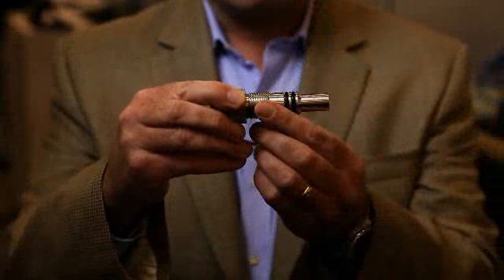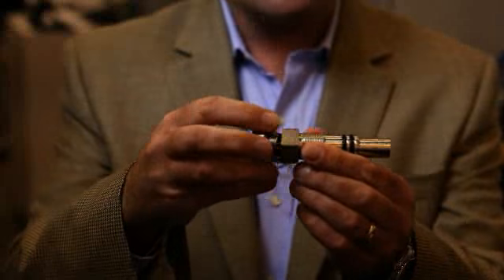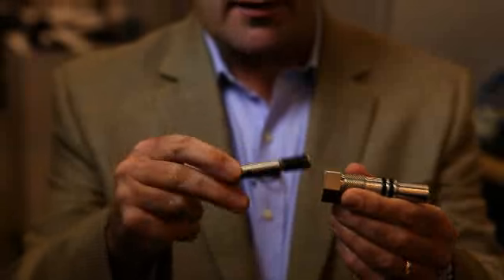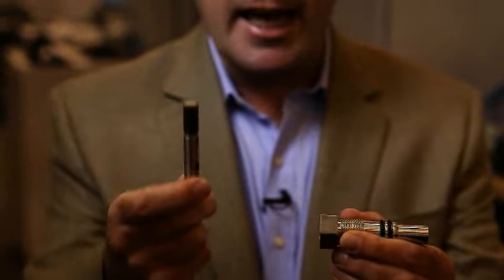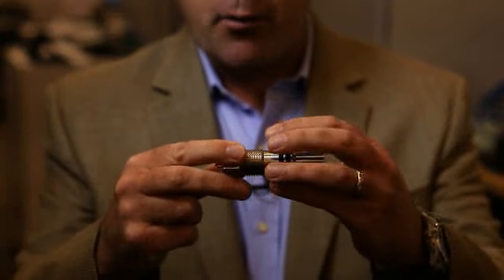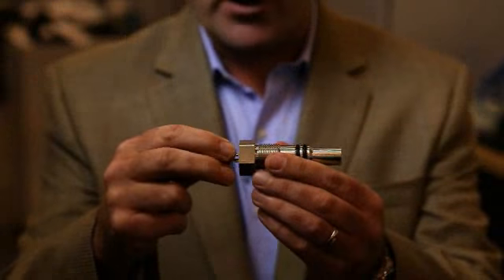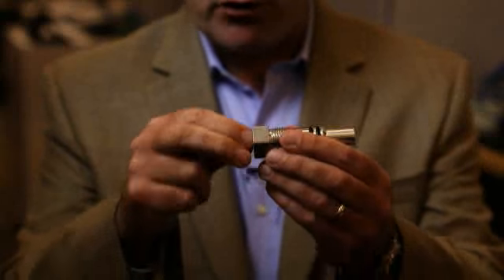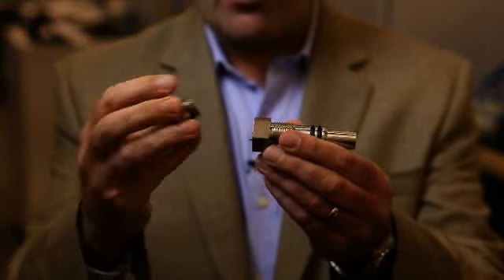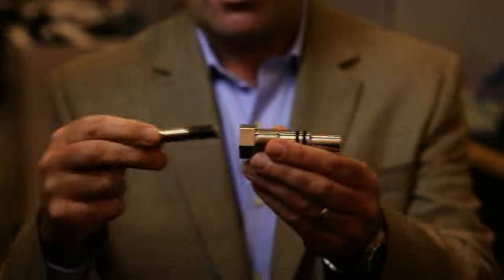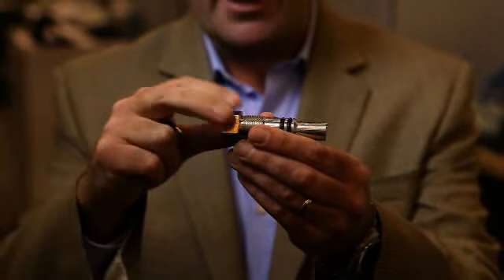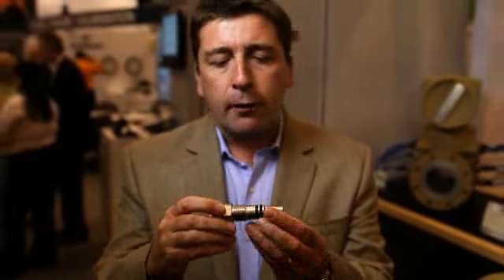This section here is the transducer holder, and this section that I'm unscrewing just now is the transducer retaining ring. The transducer itself is actually located inside the transducer holder, and it doesn't actually see any of the process. The transducer housing is actually the pressure retaining part, and this is the wetted part that's in contact with the process. So, in the unlikely event that something goes wrong with the transducer, we can come along, remove the retaining ring, extract the transducer, make an exchange, and then place the new transducer back inside the existing pressure retaining ring. There is no need for us to depressurize the line. There is no need for us to power off the meter, because the transducer housing is acting as the pressure retaining part, and the transducer itself is an intrinsically safe design and basically doesn't have enough energy there to create a hazard in the field.